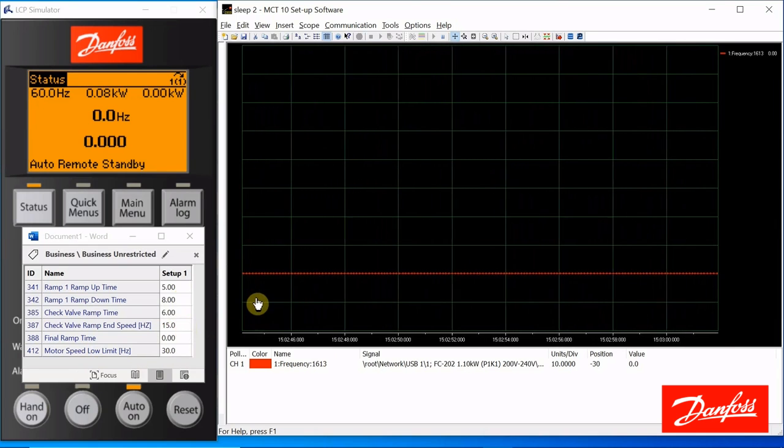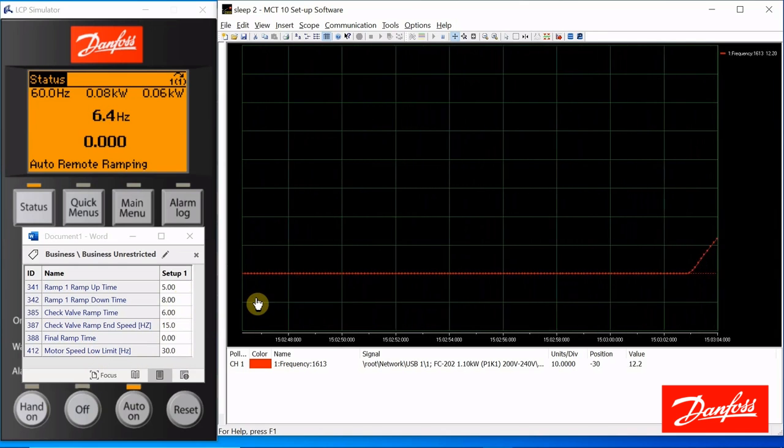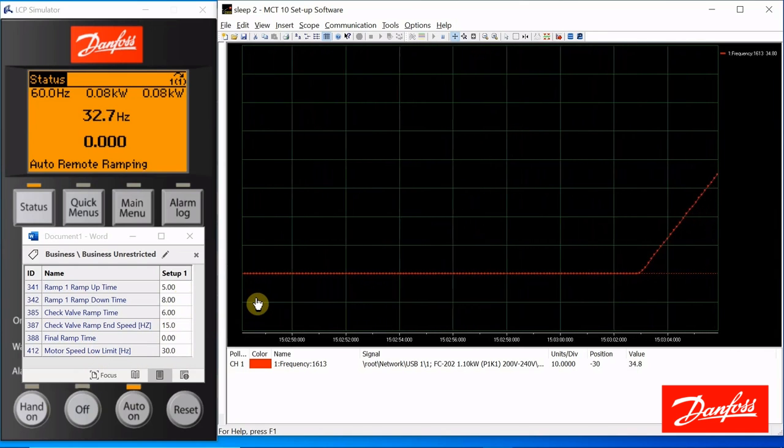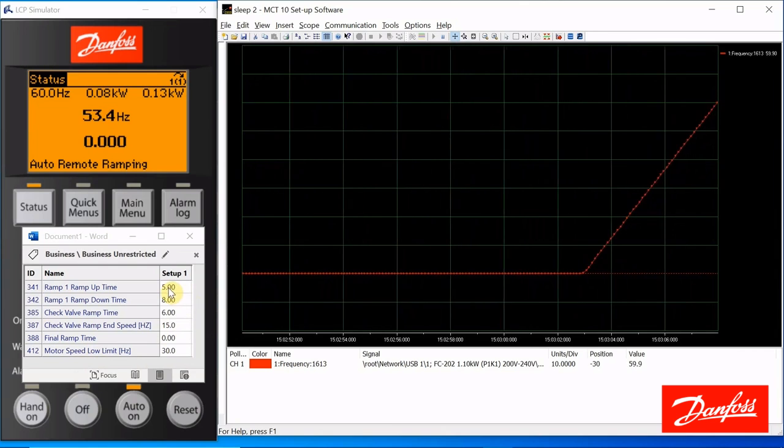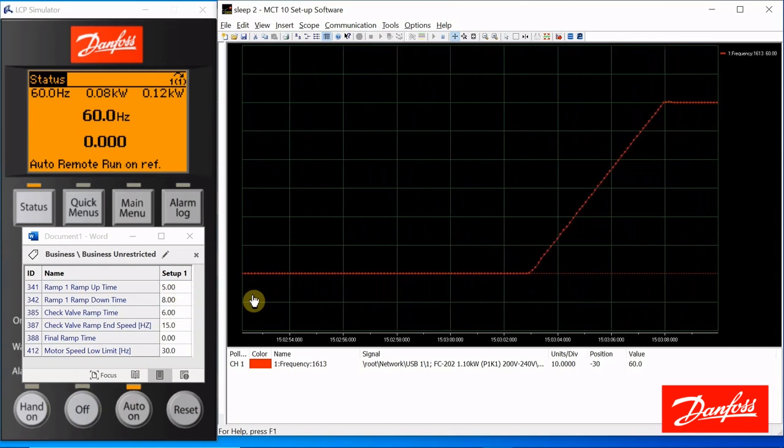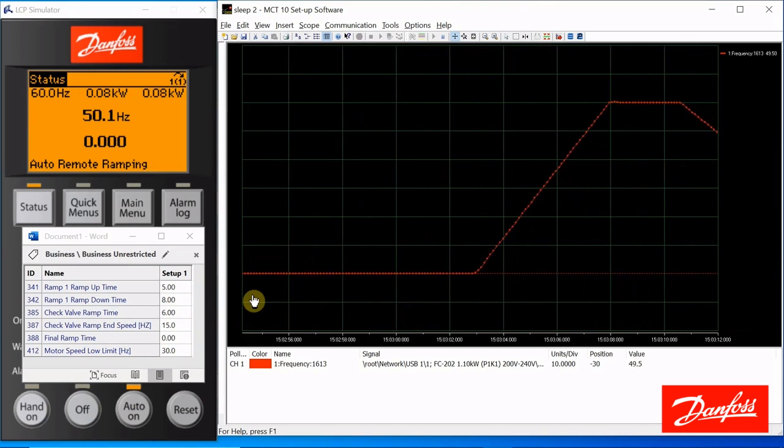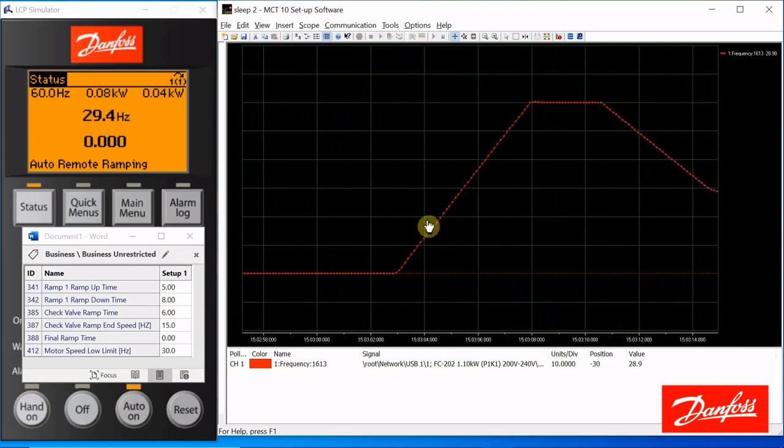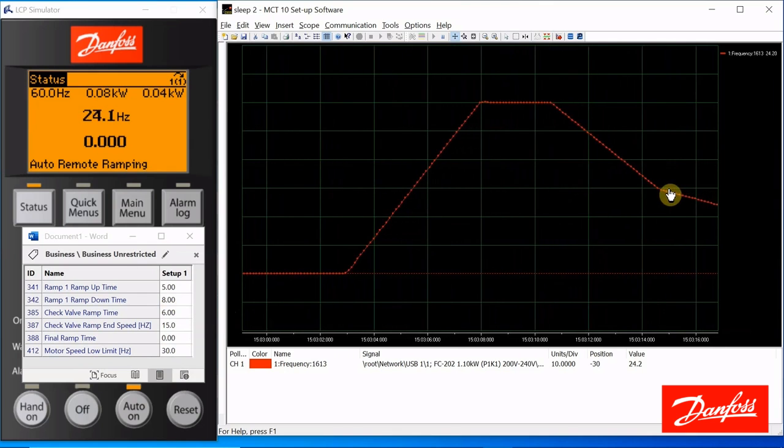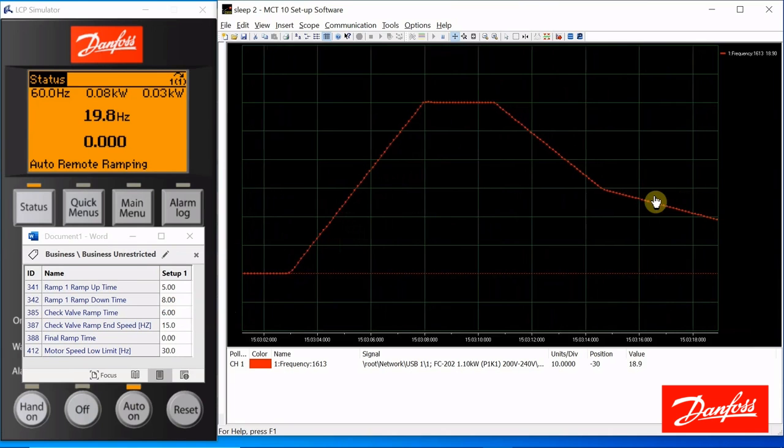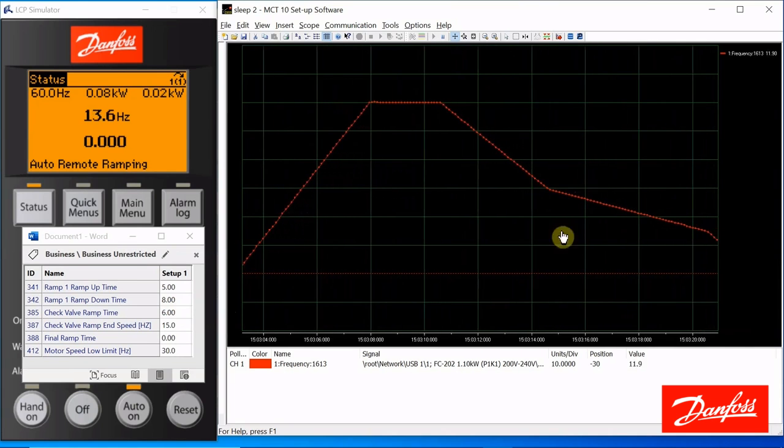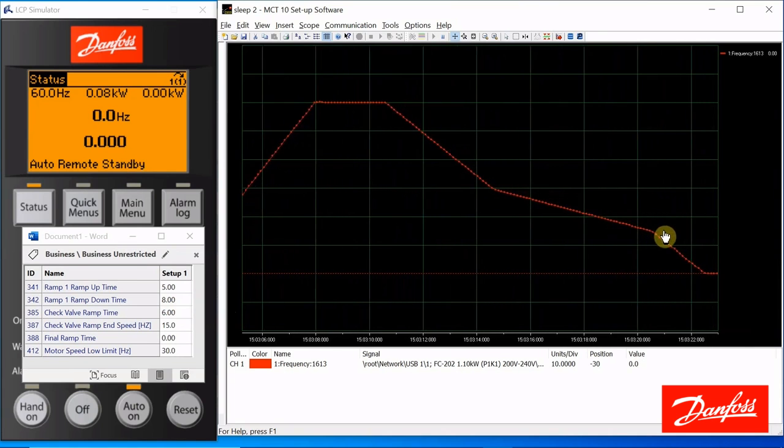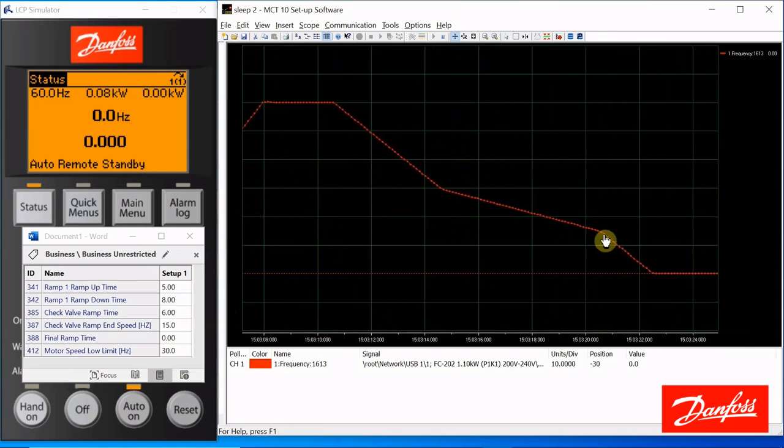Let's see how it looks. Give it a start command. We're ramping up to 60 hertz following our 5-second ramp up time. Give it a stop command. It begins ramping down at this rate, 8 seconds. Once it reaches 30 hertz, it switches over to the end ramp and takes 6 seconds to get from 30 hertz down to 15, and then resumes that 8-second pace.